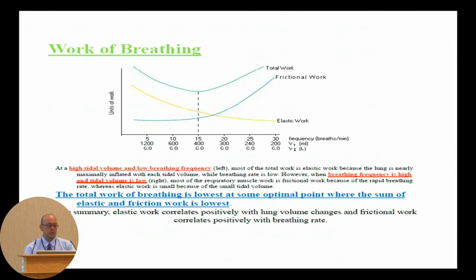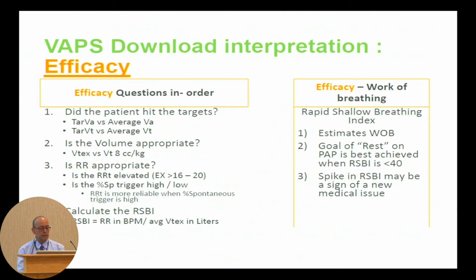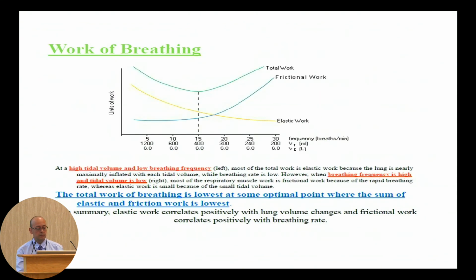So basically, when we're doing non-invasive ventilation, we are trying to reduce the work of breathing. You see this line is the total work. This is the tidal volume, basically elastic work. And this is your airway resistance. And you see that the least amount of work is when you have higher tidal volumes and a lower respiratory rate. So as we were seeing in the prior slide, when monitoring your respiratory rate, if it's elevated more than 15 or more than 16, that means the patient is working too hard. That means you need to adjust your IPAP parameters or your I time.